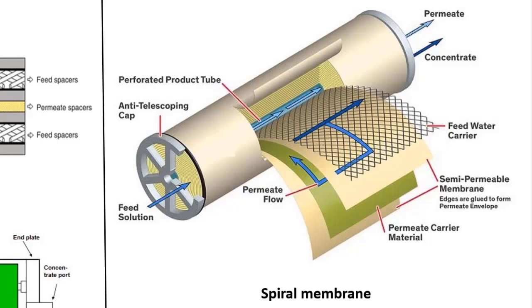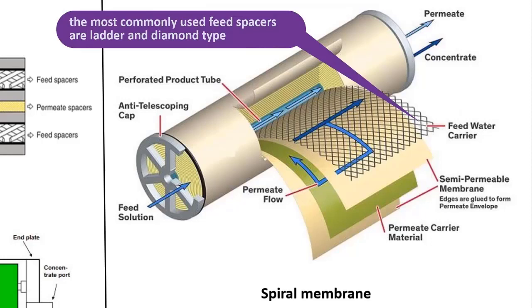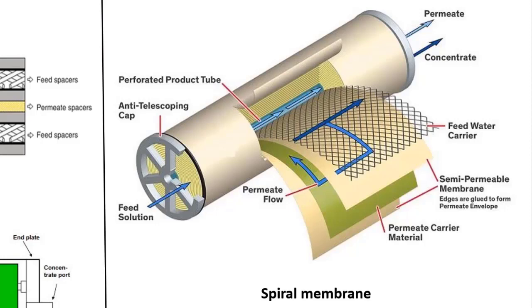There are many different types of feed spacers in the market, but the most commonly used feed spacers are ladder and diamond type. Feed spacers are usually made of plastic polypropylene. The operating mode in this type of membrane is cross flow.